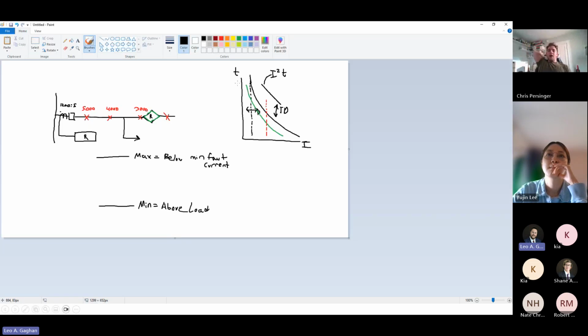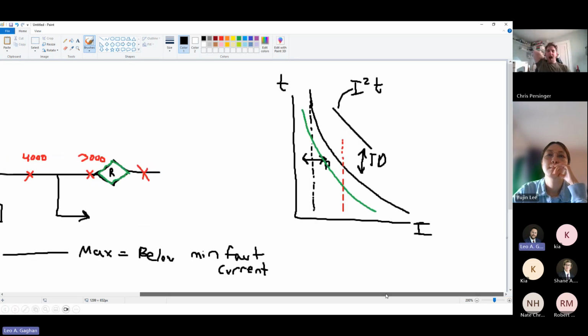When that comes into play is when we're looking over here. We're saying, okay, we've got to be faster than that equipment damage curve, and we've got to be slower than that downstream recloser. Yes, anything from 1.2 to 1.5 is acceptable. I just know that as I change that, my curve is going to move left and right. My goals are to be faster than the damage curve and slower than the recloser. What works best, moving me left and right, to accomplish my goals? So there's a little bit of discretion there. Usually it takes a little bit of fine tuning.